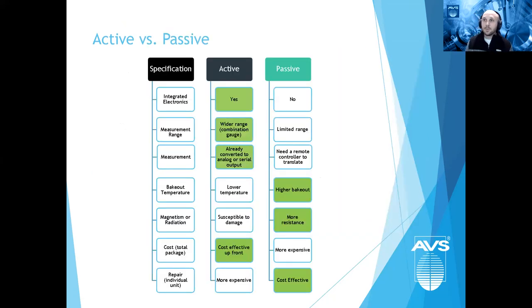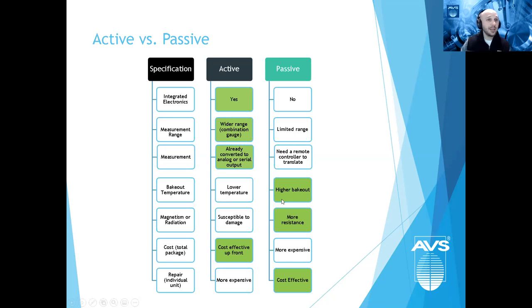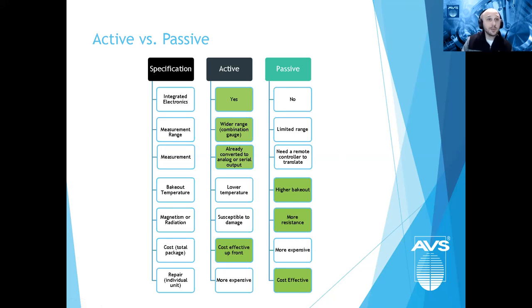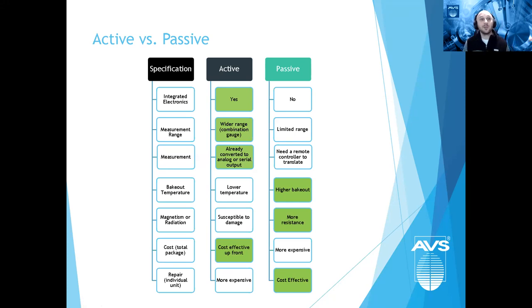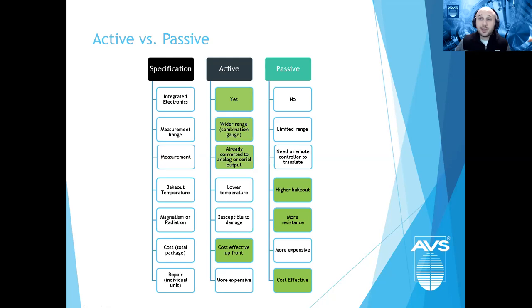Why not always use active gauges? Passive gauges, without fancy electronics, typically offer a higher bakeout temperature — necessary for UHV — and are more resistant to radiation and magnetism. The passive gauge itself is also more cost-effective to repair or replace. However, since you need a remote controller, the upfront cost for a passive system is higher. The cost of ownership over time, replacing passive transducers, is typically more cost-effective. It depends on your application: do you need UHV bakeout, magnetic/radiation resistance, or just pressures down to 10⁻⁶ or 10⁻⁷?